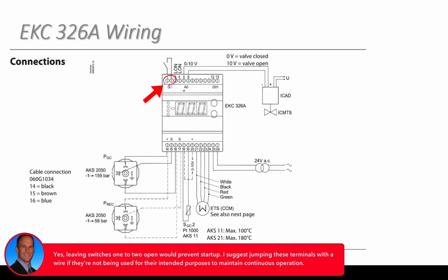And this would probably be something you'd notice right away on a startup. Yeah, I think I've got everything in place. Why isn't the controller operating? Why aren't my valves starting to modulate? Yeah. And you would get an error code that's related to this, and you would know that that's exactly what that means, that those 2 terminals have to be jumped out.